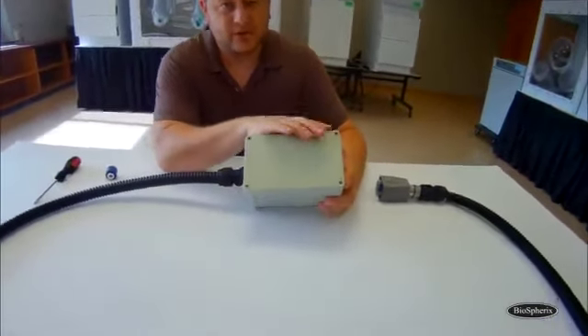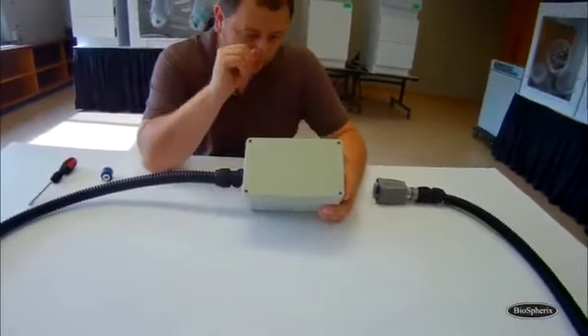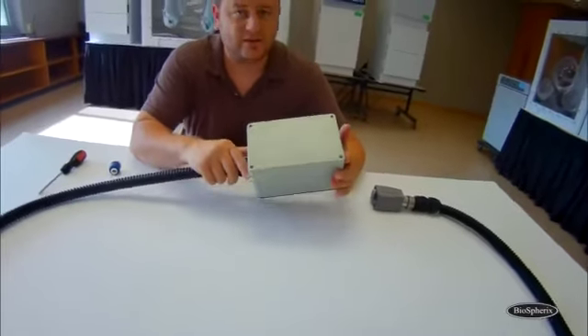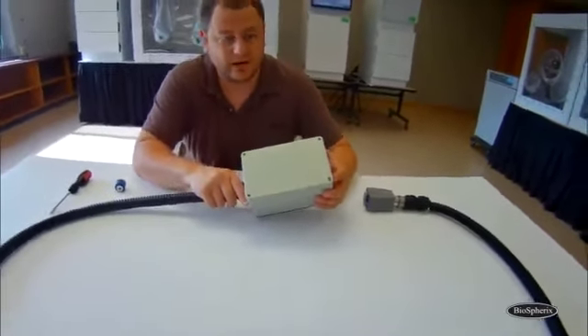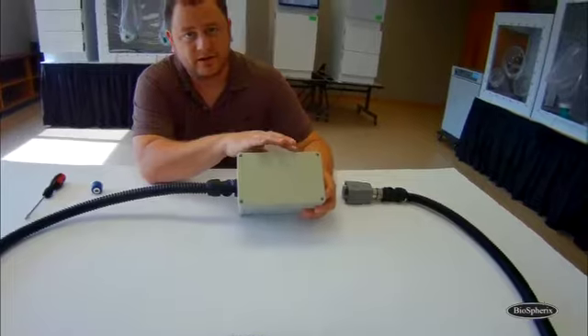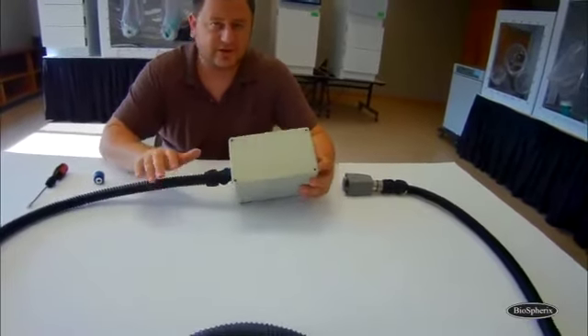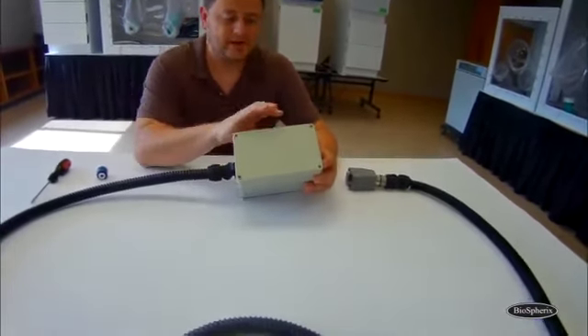Now, whenever you change one of these oxygen sensors, these model E445s, it is a good idea to recalibrate before using. A new sensor is going to have different calibration coefficients than your old sensor, so make sure once you change it, recalibrate.